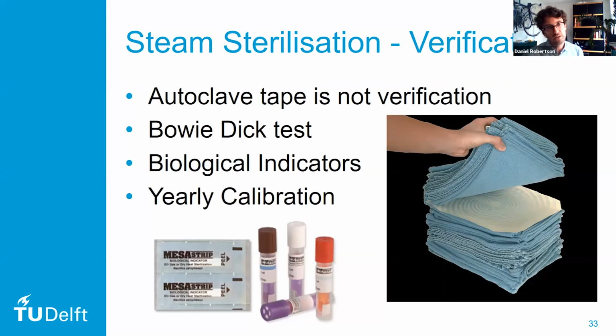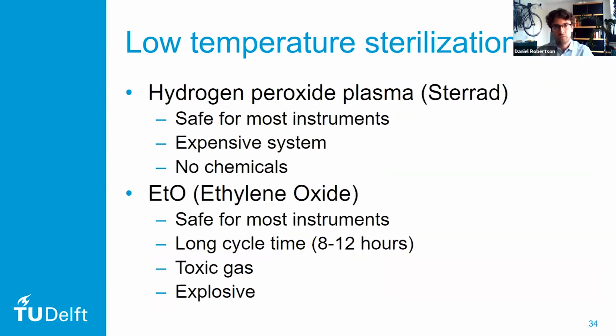And the last important thing is that autoclaves always need a yearly calibration. So probably the company that has installed the autoclave for you comes around and does a check on your autoclave to see if it still functions, and it has to be cleaned. All the lime scale has to be removed from the device. So when maintenance is performed on your device, you should ask the company that comes around to perform one of these process verifications.